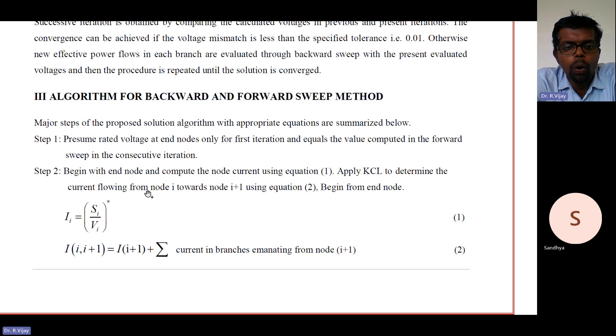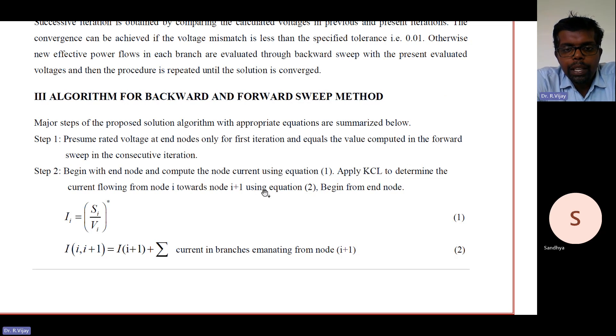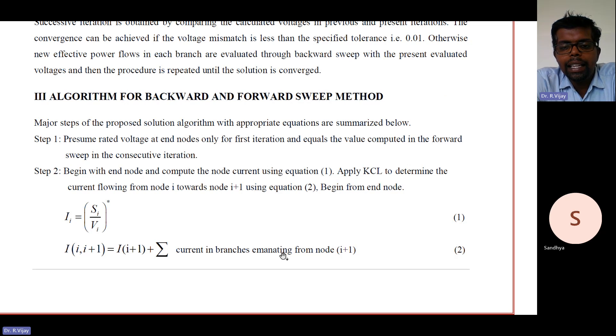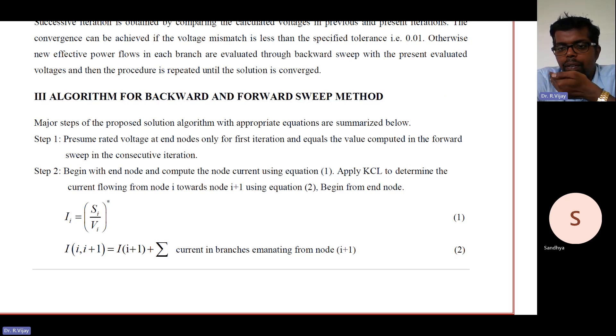Apply KCL to determine the current flow from node i towards node i+1 using equation 2. Begin from the end node — in the backward sweep algorithm, the procedure starts from the end node. Calculate the current using Kirchhoff's current law. Equation 2 is: I(i, i+1) = I(i+1) + summation of currents in branches emanating from node i towards node i+1. We start from node i and proceed towards node i+1, beginning from the end node.